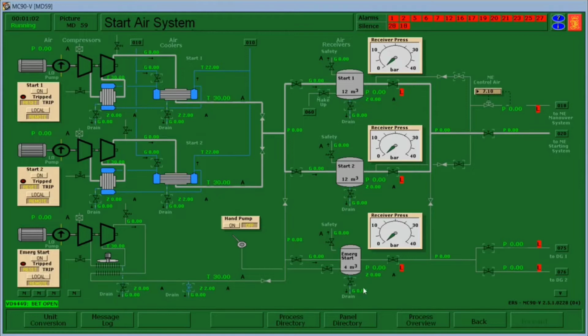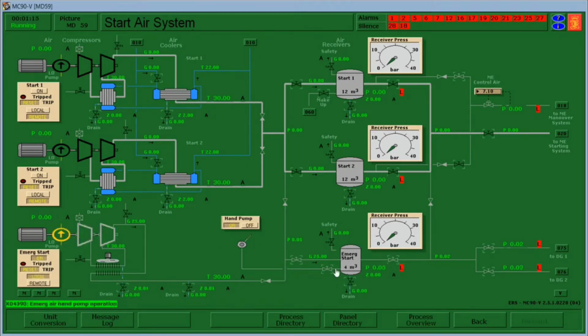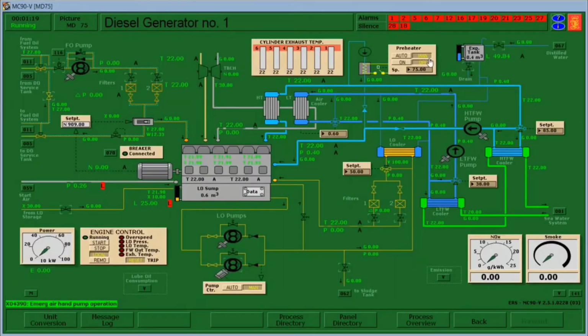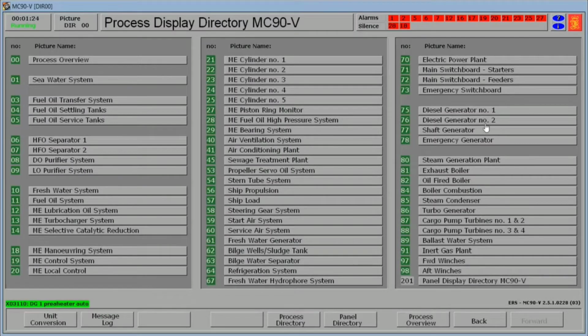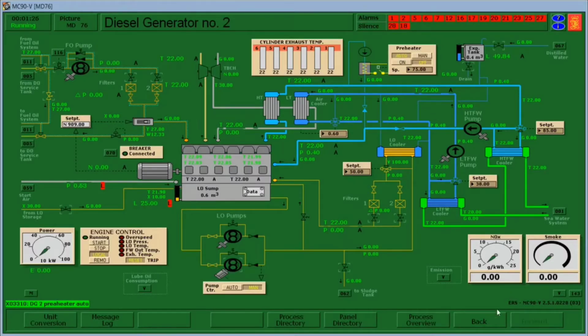We drain the water, open the inlet valves. I'll open the hand pump for fast operation. Close the drain, set to local. Then proceed to diesel generator number 1. Set the preheater to auto and generator number 2 set to auto.